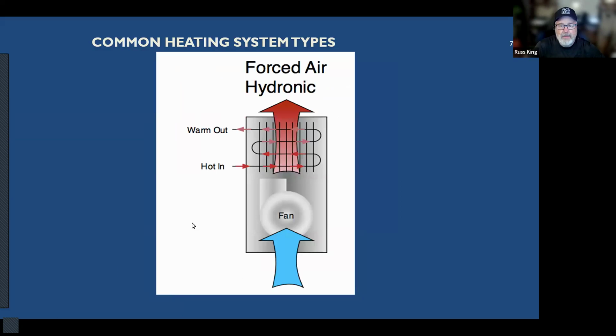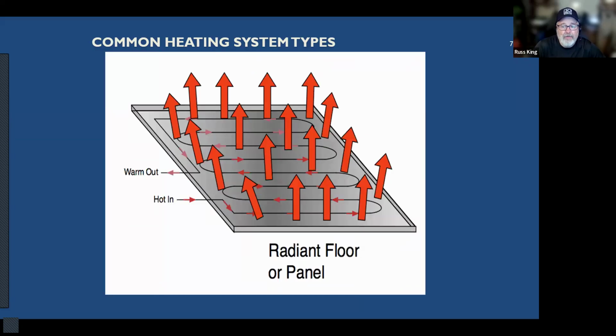The forced air hydronic, as I mentioned, you've got hot water coming in and you blow air across that, and then warm water comes out. We call that forced air hydronic. Another type of hydronic is radiant floor panels. You're bringing in hot water, you're running it through the floor under the slab. The slab gets nice and warm, and it radiates heat into the space. So it's a very nice form of heat. Okay. And then that water goes back, it comes in hot and it comes out warm, and it has to be heated back up. Okay.